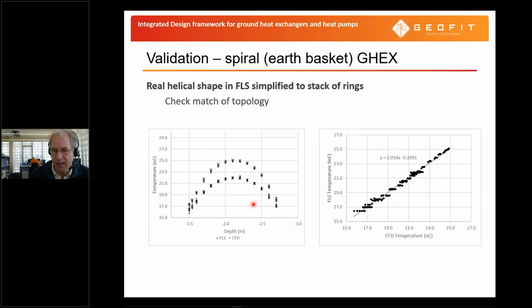So we are not introducing any errors because of a shift in depth and an error between the actual Z position and the difference between a completely horizontal ring or actually a slightly inclined helical turn of the total spiral. We can also plot it here, where we have the temperature calculated in the CFD simulation and the temperature calculated in the FLS, in the analytical solution. And you can see here that, well, let's say the angle, it's almost 1. So, you know, there's a very good match. And then there is a constant offset of around 0.2 degrees. So the overall error is on the order of 0.2 degrees Kelvin in absolute error, which is pretty good.